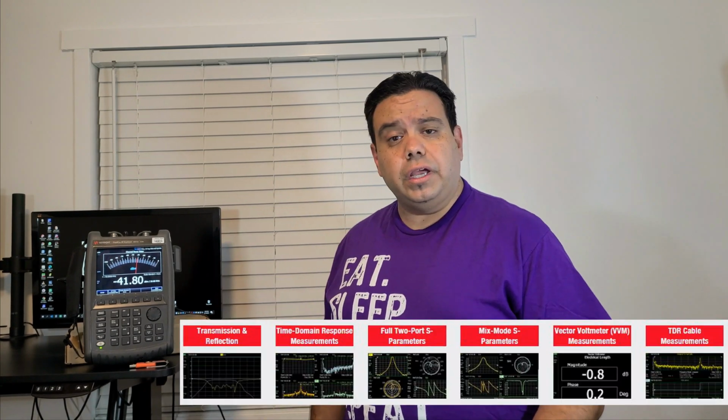The Keysight FieldFox is a handheld combination analyzer that's capable of being many instruments in one, anywhere from a spectrum analyzer to a vector network analyzer to this channel power meter that you see here that I have on display today. Most of the options that are available for the Keysight FieldFox are available via a simple software keycode upgrade. There are also trial licenses available at keysight.com where you can try any option free for 30 days. Today I'll show you how to download a permanent license and install it on the Keysight FieldFox with a simple USB memory stick. Let's check it out.